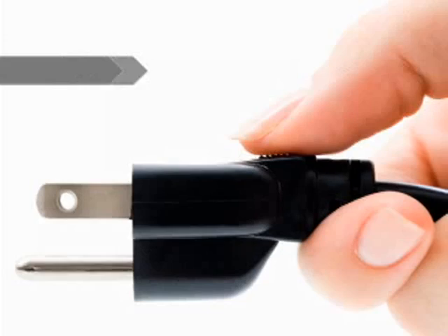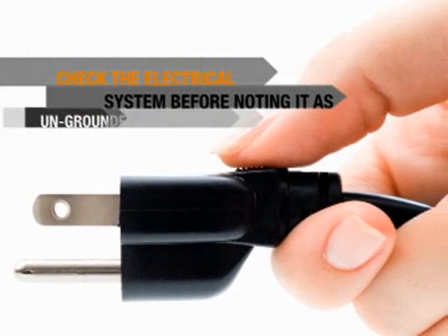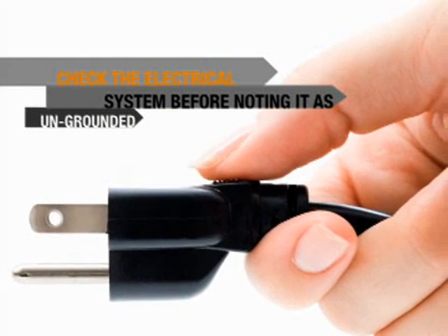and the branch circuit wiring needs to be able to extend the system ground to the receptacle it ultimately attaches to. Again, two-prong receptacles may indeed be grounded. Three-prong receptacles enable that receptacle to extend the system ground to any device which may require it. So before you call out that a system is ungrounded merely because it has a two-prong receptacle, you need to check the system itself. You want to be right with the advice that you give to that homeowner.